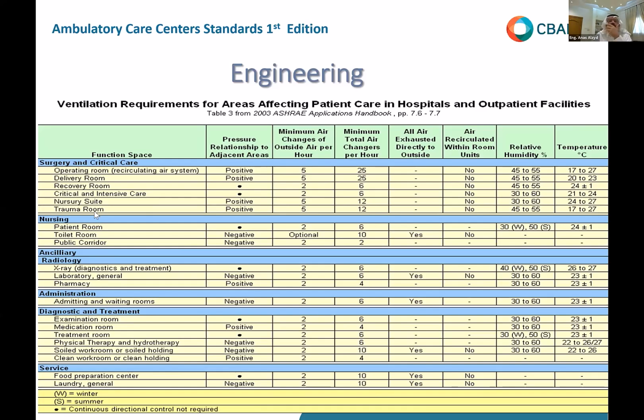This is an example of ASHRAE for hospitals and healthcare. For example, for the examination room here, they tell you it doesn't have to be positive or negative, okay? However, you need to have 2 minimum air changes from outside. So you have to have 2 air changes per hour from fresh air.